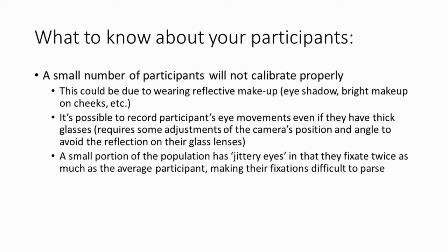So you can just ask them to come back at another time, or just run them through the experiment, give them their credit, and know that you can't use the data. With this EyeLink system, it is possible to record participants if they have thick glasses, even ones that are curved quite a bit. We had one issue with a participant that we figured out later that we could have fixed, but this requires some adjustments of the camera to change the angle of reflection of the screen, which again is very easy, and it still records their eye movements with similar accuracy.